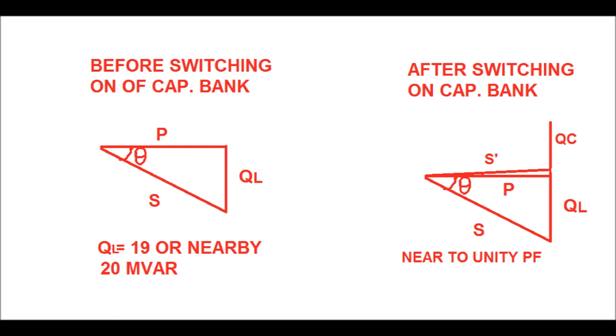Now, how does the capacitor bank improve the power factor of the system? In the left side of the diagram, before switching on the capacitor bank, the power triangle is shown. Here Q_L is the reactive power, P is the active power, and S is the apparent power. Power factor is defined as the cosine of the angle between P and S, or the ratio of active power to apparent power.